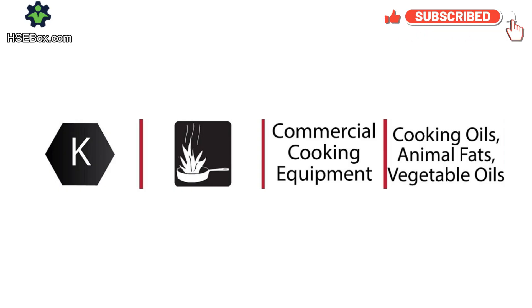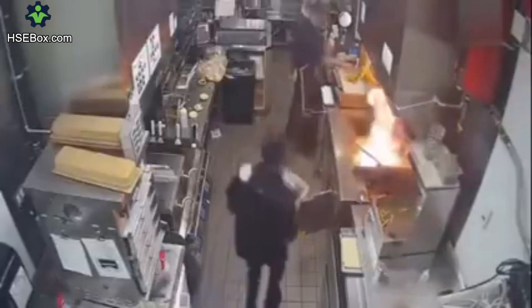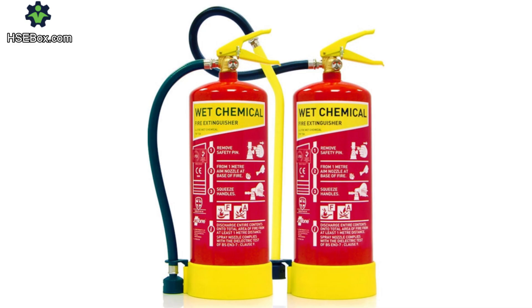Finally, we have class K fires, which involve cooking oils and fats. These are typically found in commercial kitchens where large quantities of oil are used. Pouring water on a grease fire is extremely dangerous, as it can cause the oil to splash and spread the fire even further. Instead, wet chemical extinguishers are used — these work by cooling the fire and forming a soap-like solution that cuts off the oxygen supply. Think of a deep fryer catching fire in a restaurant; this is the perfect example of a class K fire.